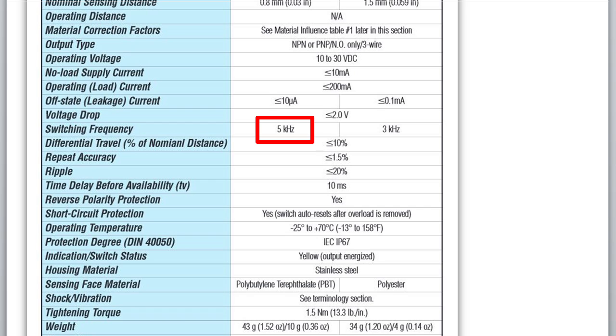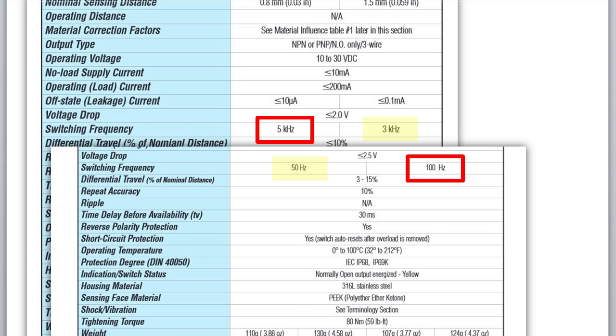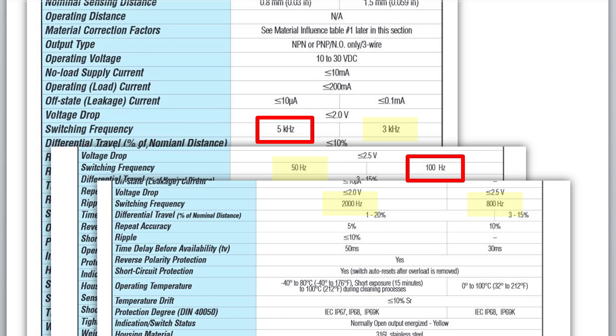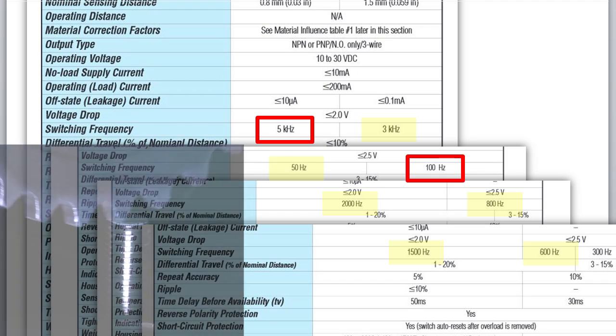Keep an eye on the switching frequency of the sensor. Looks like this one is 5000 Hz but you might see some that are 100 Hz. So if you are trying to detect objects moving by faster than 100 Hz, like gear teeth for example, and you are using a 100 Hz sensor, then you are going to miss some of the objects.